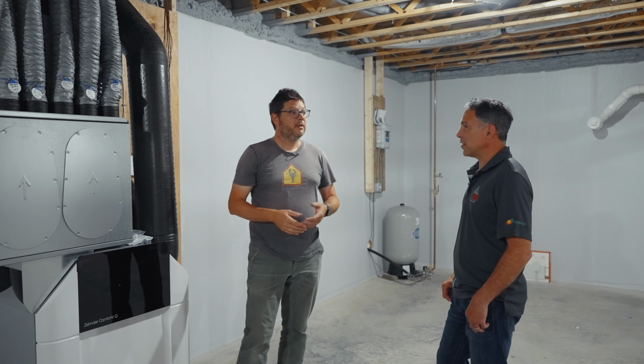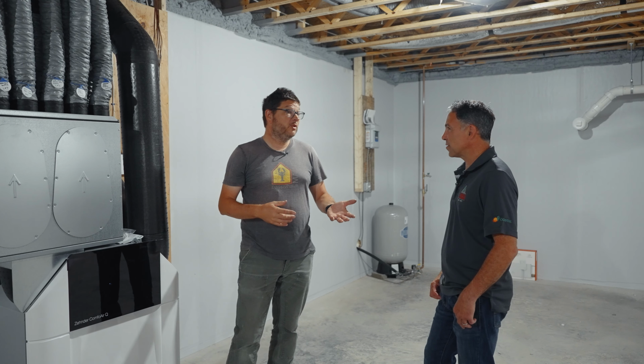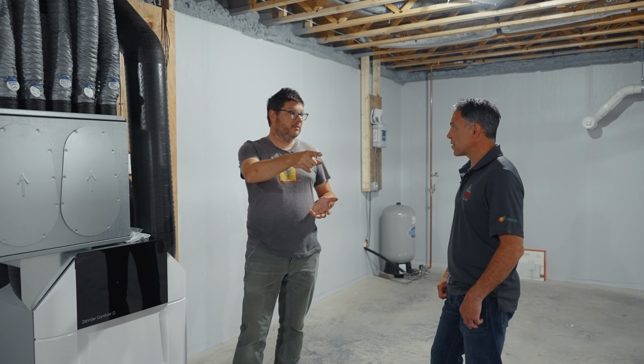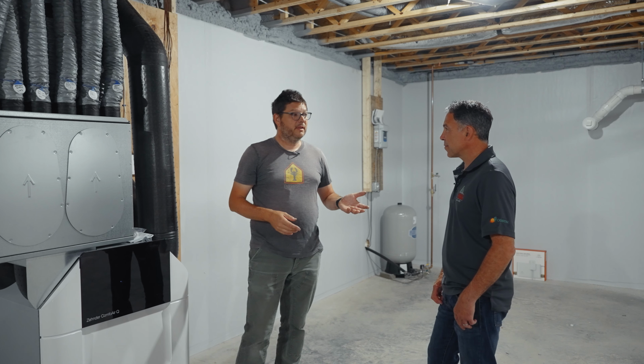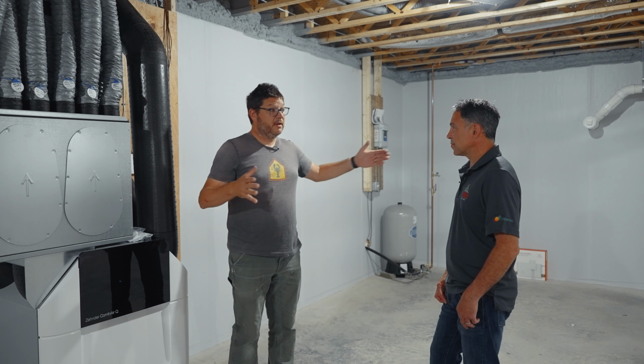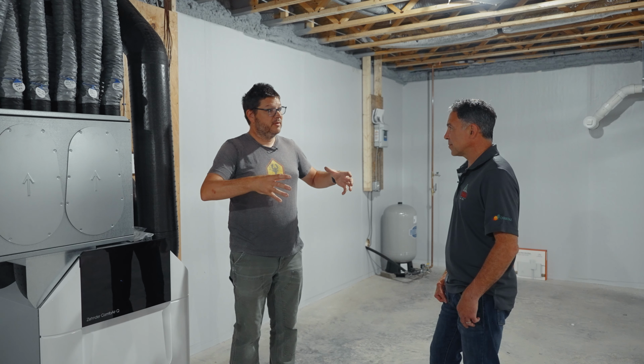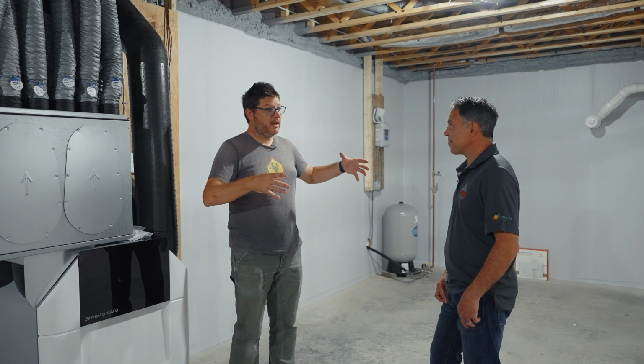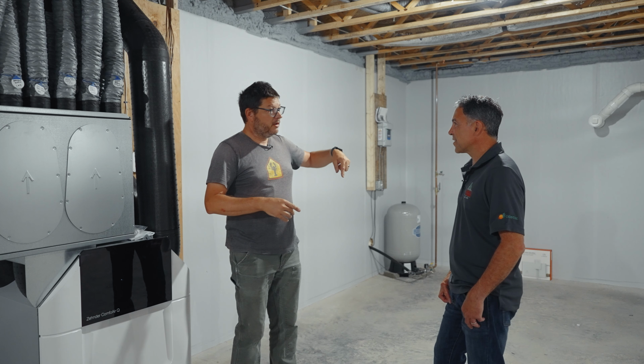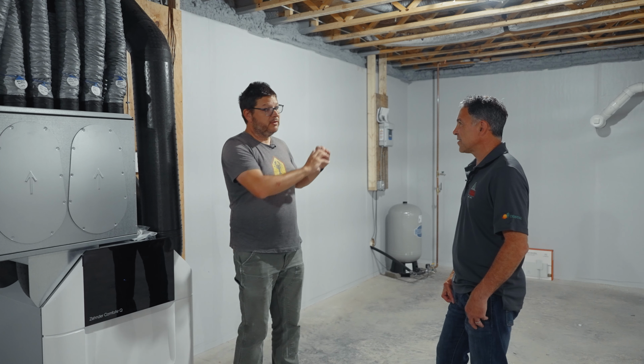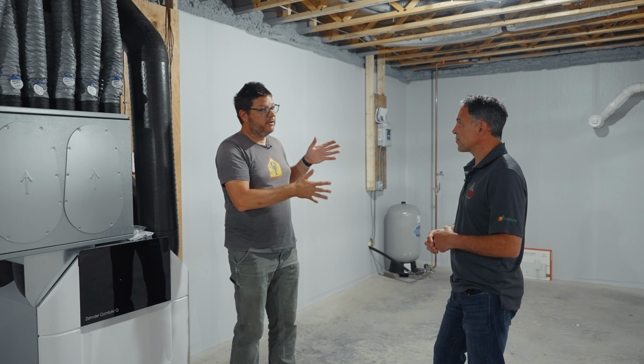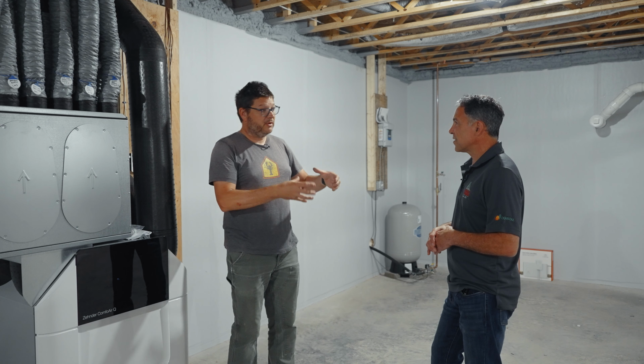Every time you change the size of a duct, change it from sheet metal to a flex duct, put an elbow in it, the airflow changes. So you've got to check each one individually as its own. One of the things we do is when we engineer the heating and cooling systems, we actually hire a mechanical engineer that will design the ducts in our space. So they'll tell you, I want 20 feet of this size, and you're going to use this transition here, and then you're going to switch to this. We're going to reduce it to this here for 8 feet, and the last 3 feet are going to be flex duct to connect to this particular boot. Got it.